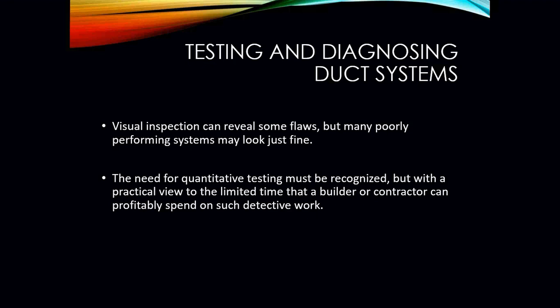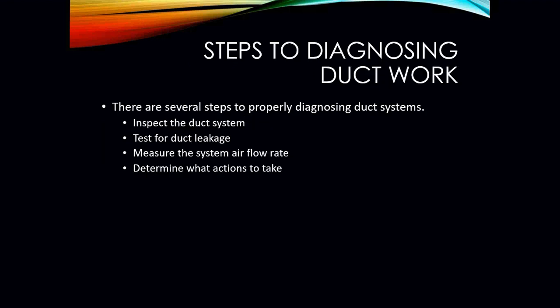When it comes to testing and diagnosing your duct system, visual inspection can reveal some flaws, but many poorly performing systems may look just fine. The need for quantitative testing must be recognized, but with a view to the limited time that a builder or contractor can profitably spend on such detective work. Which is why in many cases we are now required to have all of our ductwork properly sealed and properly wrapped, to eliminate these possible issues of losing valuable heat and air conditioning to spaces where we personally don't care.